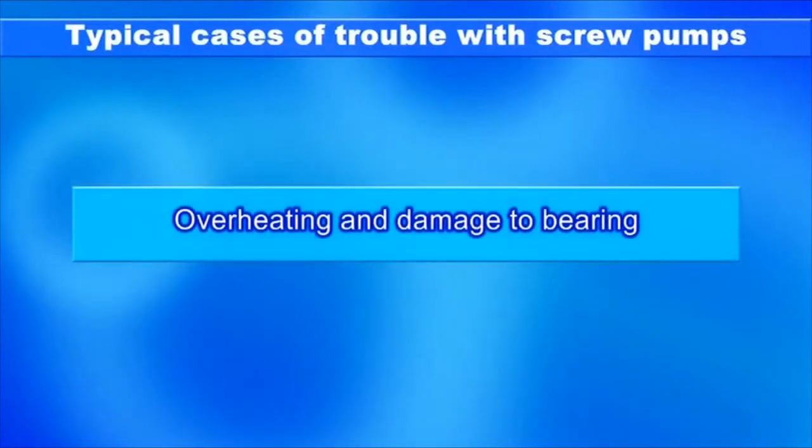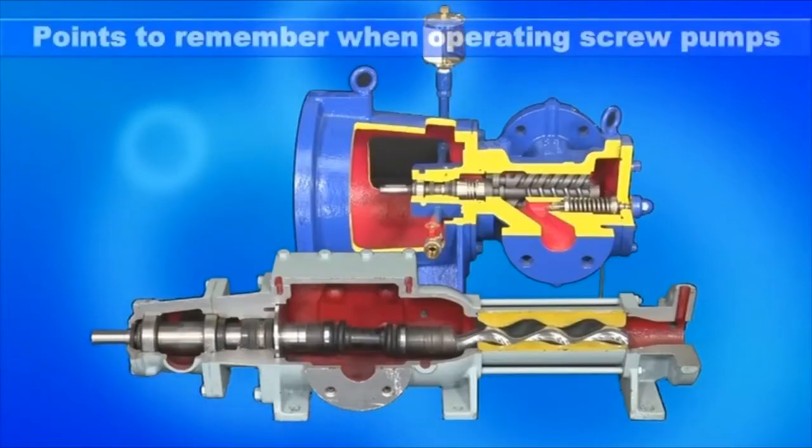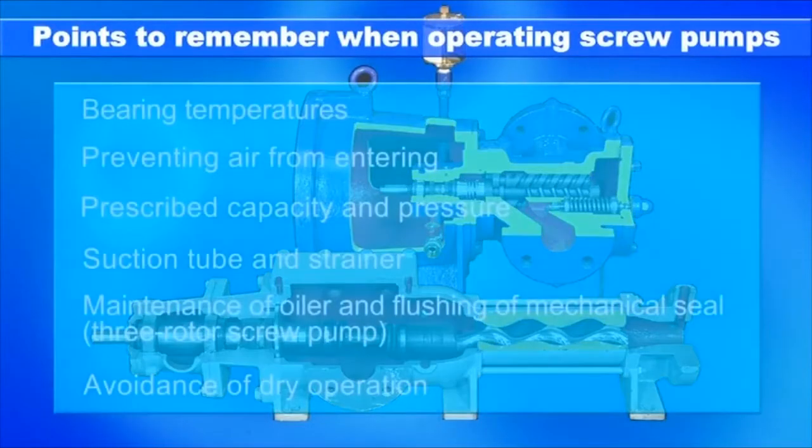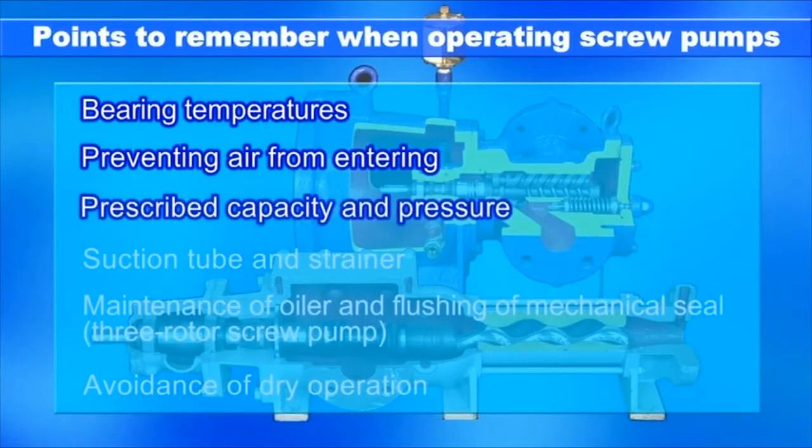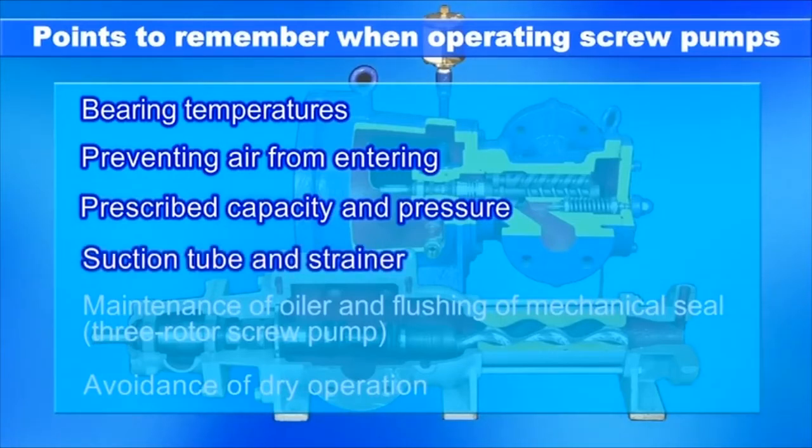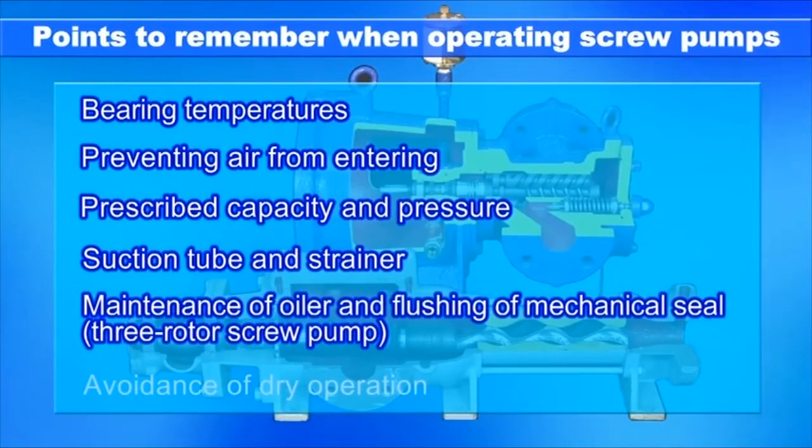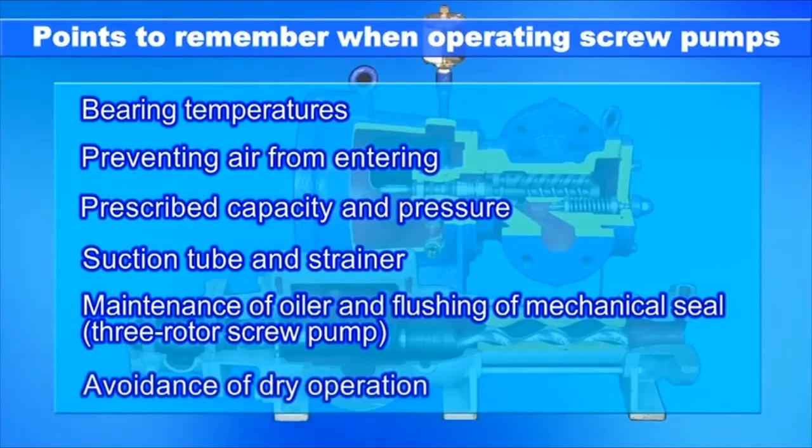Typical reported cases of trouble with screw pumps have concerned overheating of and damage to bearings. Be mindful of the following points: the rise in bearing temperatures, preventing air from entering, keeping pumping capacity and pressure within prescribed levels, clogging of the suction tube and strainer, maintenance of the oiler and mechanical seal's flushing function in the case of three rotor screw pumps, and avoidance of dry operation.